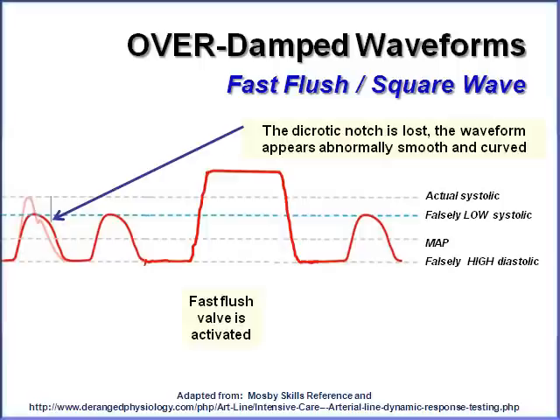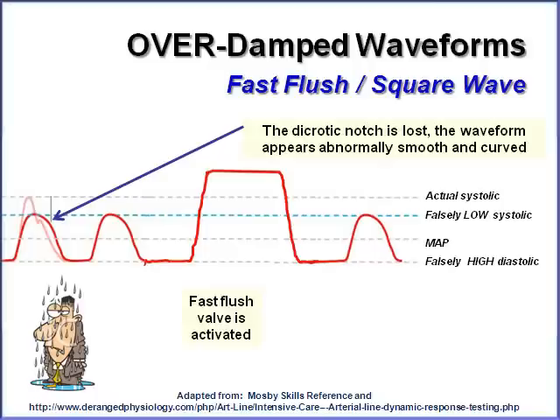An overdamped waveform is something we want to troubleshoot. On the picture, the normal arterial line waveform is highlighted in pink, and when you look at the red waveform, the dicrotic notch has been lost. When we do our fast flush, it's a slow upstroke that slowly comes back — there are no oscillations afterward.